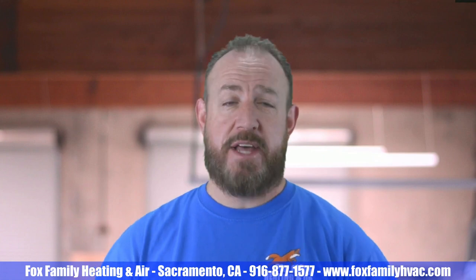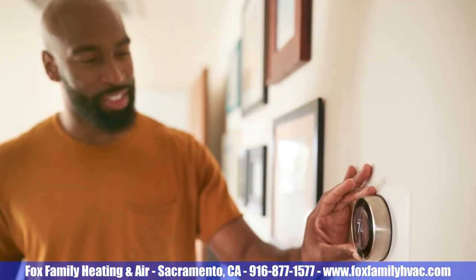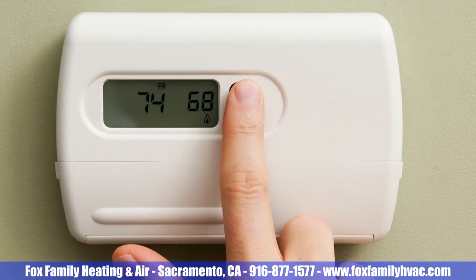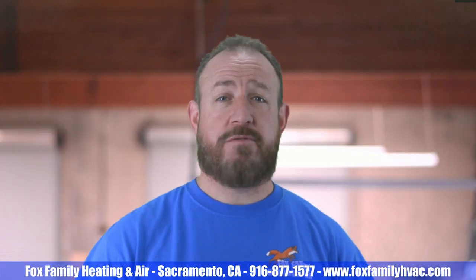Let's check your thermostat and see if it's displaying properly. It doesn't necessarily mean your furnace should be working properly if it does still display right — it's just where I always start. Some thermostats only run on the 24 volts provided by the furnace, and some thermostats have AA battery backup. I just want to know if the system is calling for heat or not.